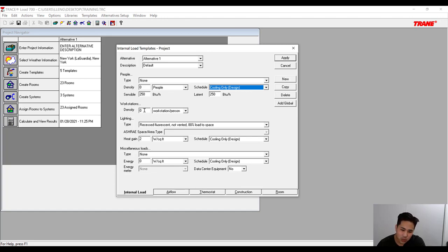For workstations, we'll keep it at zero workstations per person. For lighting, we're going to keep it at one watt per square foot, which is an average watt output per square foot for lights. We'll keep the schedule at 'cooling only design.' Miscellaneous loads we'll keep at zero as default.